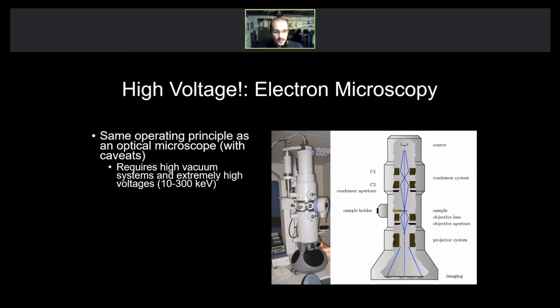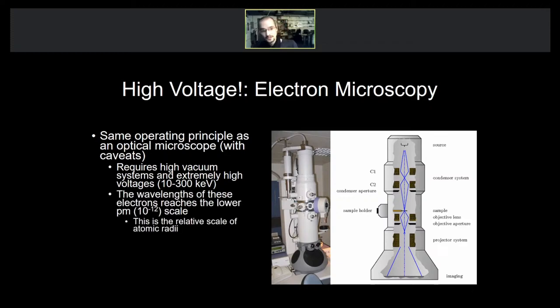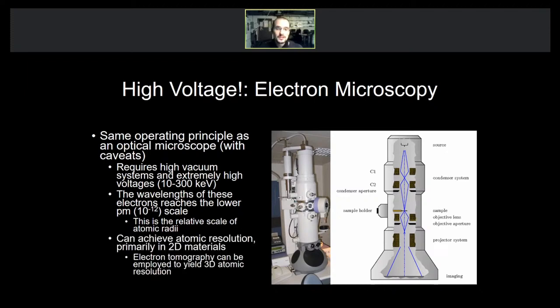Electron microscopes use extremely high voltages between 10 and 300 keV. This accelerating voltage drives the electrons forward at incredibly high velocity, tuning their wavelength via the de Broglie equation — since mass is fixed, velocity changes the wavelength. The wavelengths of these electrons can reach the lower picometer scale, relative to atomic radii. You can ultimately achieve atomic resolution and do electron tomography with electron microscopes. However, atomic resolution is primarily achievable in two-dimensional materials.